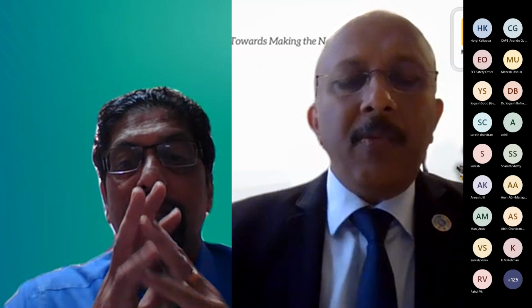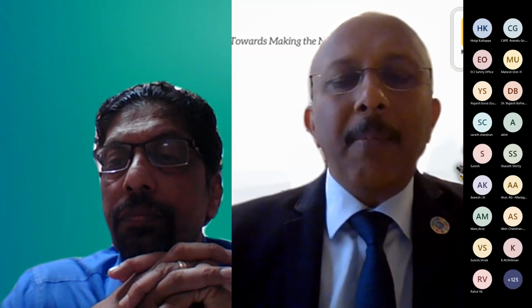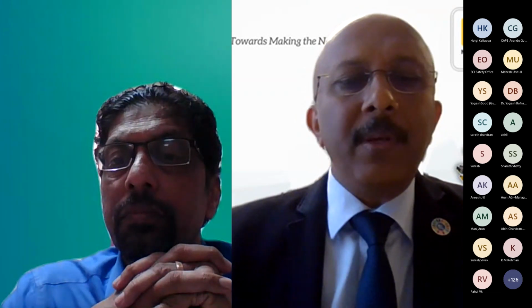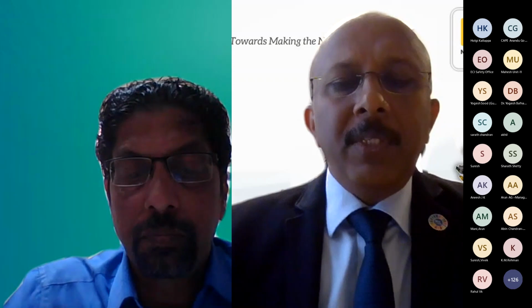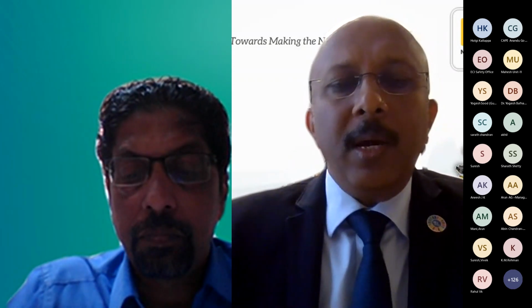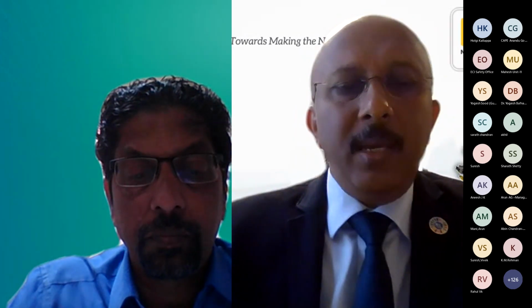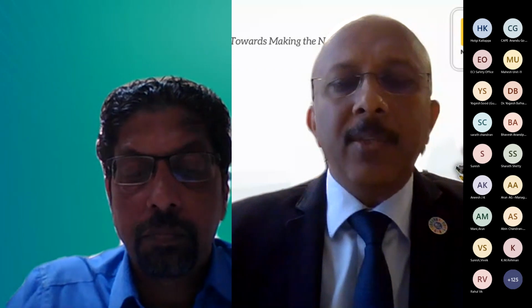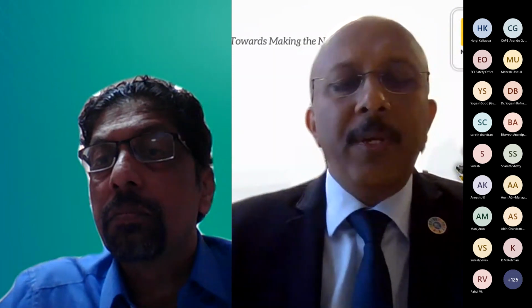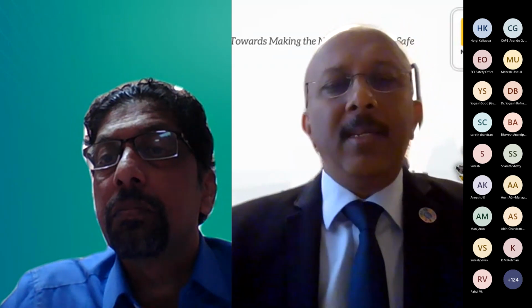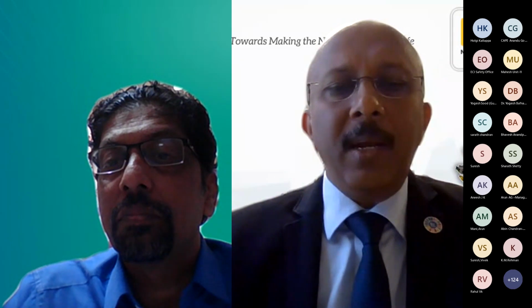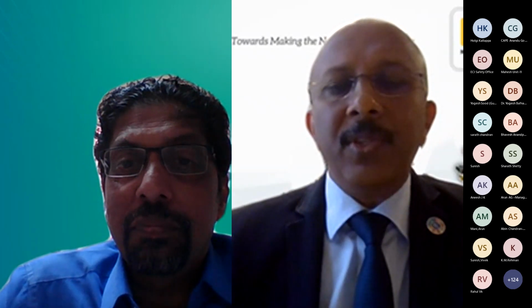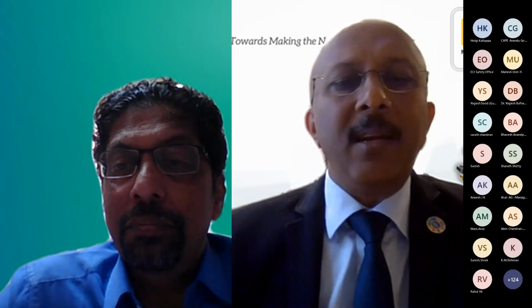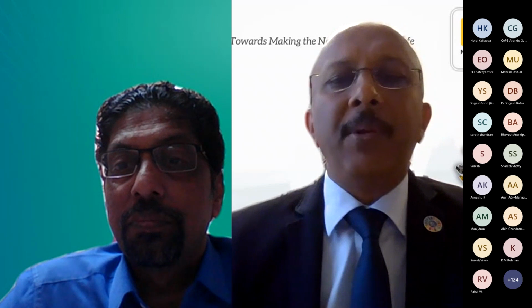Now coming back to the question, the fault return path, which is a metallic path, is most of the time galvanized steel, nothing but GI. The steel considered in the standard is grade 1, high quality steel. Unfortunately, GI available in the market is not first quality steel. It is always scrap steel, recycled steel, recycled several times, and one of the last usages of the steel is in electrical installation as an earth return path. It won't work. You have to size it at least 50% more than what is recommended in the standard.